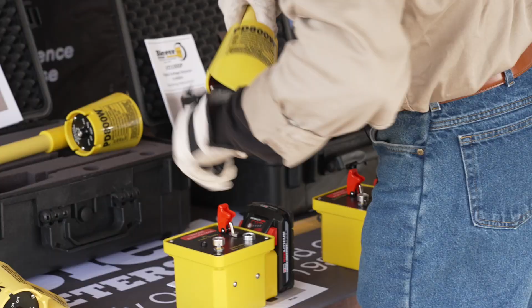Then we're going to take our PD800W, our wireless phasing voltmeter, and we tested the batteries on these. They're good. We're going to take the tool and put it in DEG for degrees. In DEG, the tool specifically looks at the phase angle. So we're going to make sure the tool's working properly on a live voltage source looking at phase angle, because we're going to do some phasing here today.